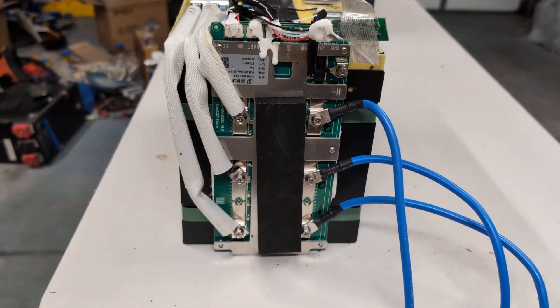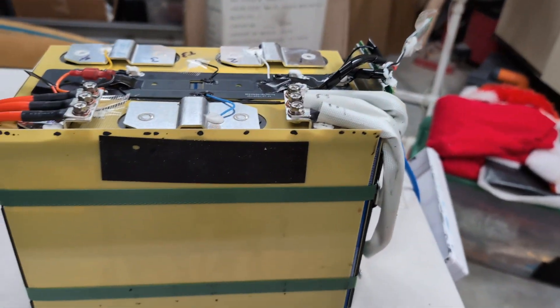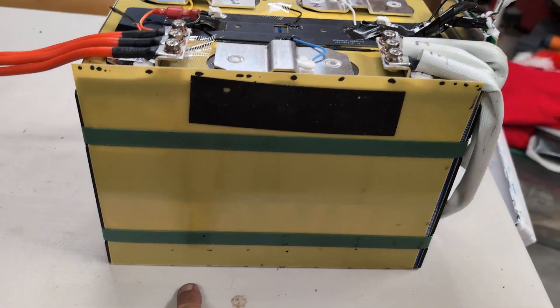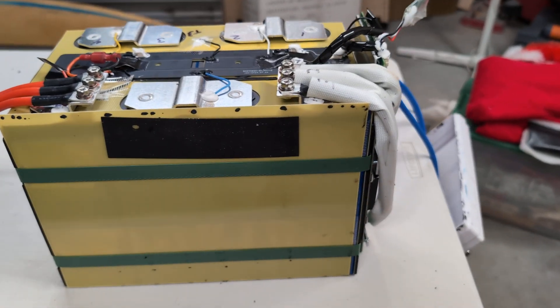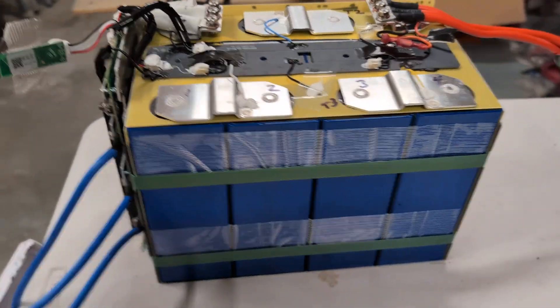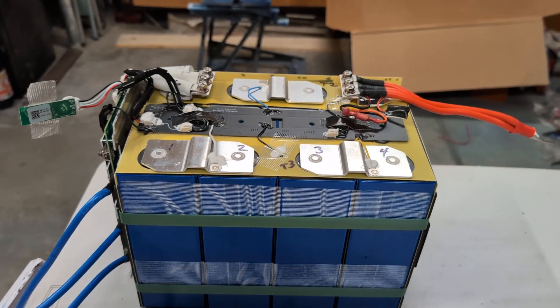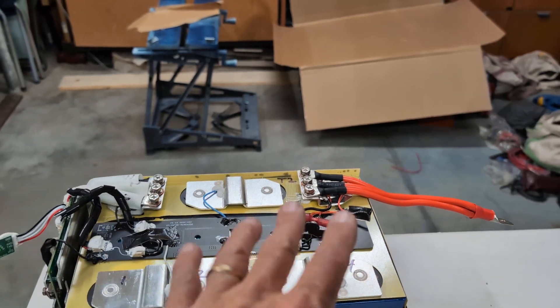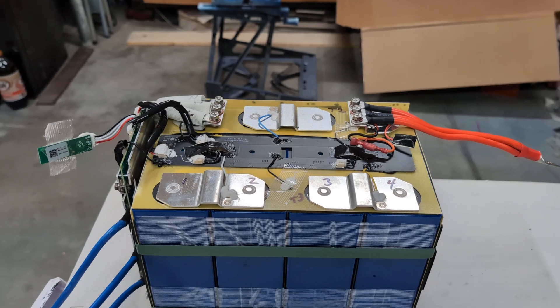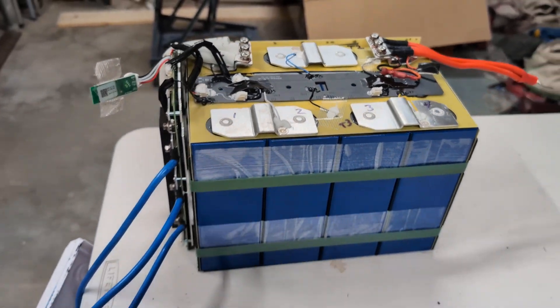Back to mechanical — this side has no label, it's pure battery with no electronics on this face. So although the instructions say to keep it vertical as shown, it could clearly lay down on this side with nothing getting damaged. Equally, I can mount it laying down on the other side — again, all battery, nothing else near the edges. We never want to put it with the lid facing down, since that's where the plastic, electronics connections, and mounting blocks are — no place for weight to rest there.